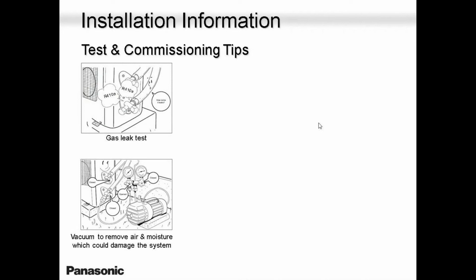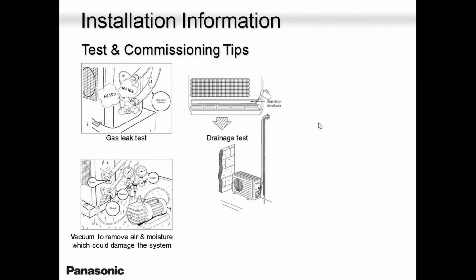I brought this slide because I have this issue at least once or twice a year. Guys are joining this, and they tell me, guess what, Paul? It works. Yeah, but every week you get calls back. I have a communication error, and then the guy powers the unit off and powers it back on, and it works. And then after a couple of weeks, sometimes maybe months, you have the same problem again. Never join the control cable, the wire that runs from the outdoor to the indoor. Please don't do that. You will always have problems.